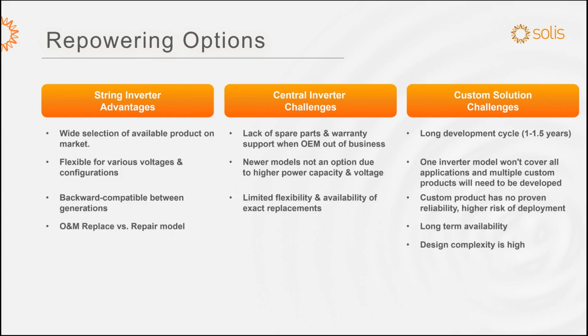Central inverter challenges: lack of spare parts and warranty support when the OEM is out of business. You could replace with a central inverter again, but it will be the same issue 7, 8 years down the line, and you will face the same problems and challenges. Newer models are not an option due to higher power capability and voltage. Most newer central inverter models are designed for 1500 volts DC applications and most are much higher power, with trending models at 4 megawatts or higher. There are some available in the 2 megawatt range, but those are pretty much obsolete models that might still be available in the marketplace. And limited flexibility and availability of exact replacement.